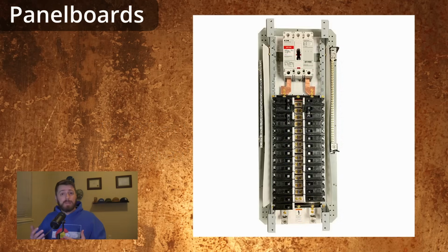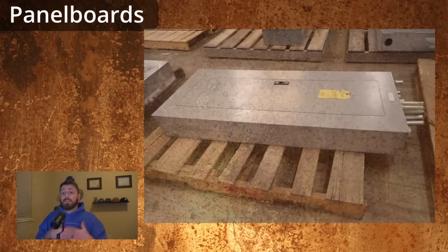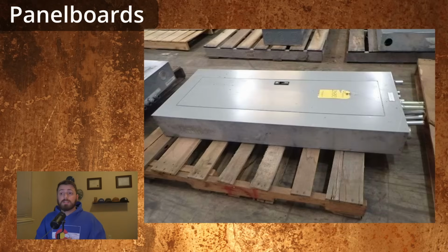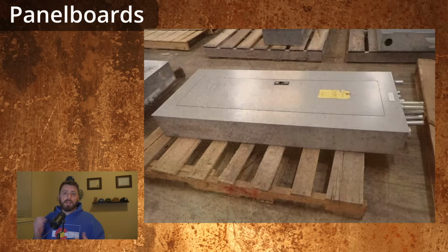The defining anatomy of a panel board is that behind the cover, the breakers are directly mounted to a vertical bus bar at the back of a fairly shallow panel board enclosure. The enclosure itself will be around 3 to 6 inches deep, and the bus bar will be mounted pretty much at the back of it. But again, you're only about 6 inches away from the main bus bar with that cover removed.